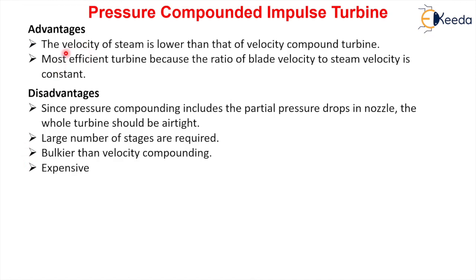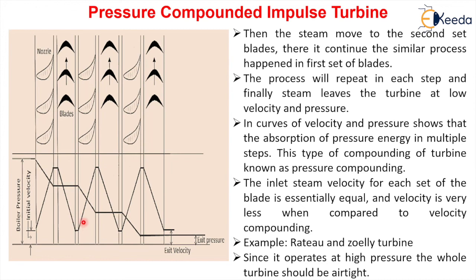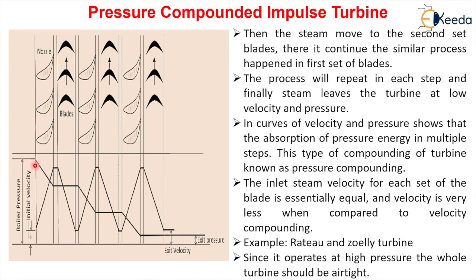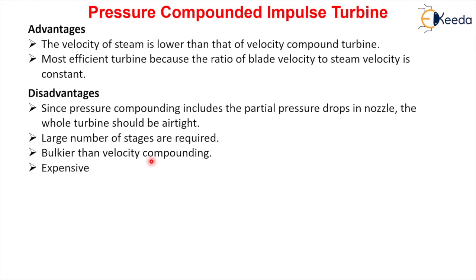Advantages of the pressure compounded impulse turbine: velocity of steam is lower than that of the velocity compounded turbine; it is the most efficient turbine because the ratio of blade velocity to steam velocity is approximately constant at each stage, giving approximately equal power at every blade. Disadvantages: since pressure drops partially in each nozzle, the whole turbine must be airtight as it operates at very high pressure; a large number of stages are required; it is bulkier than velocity compounding and more expensive.